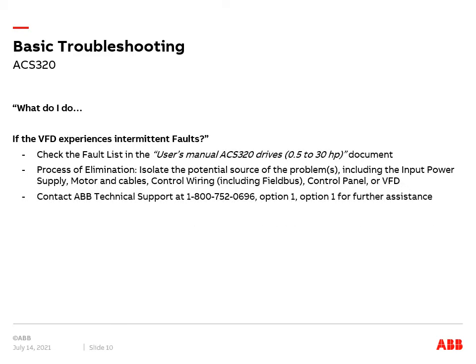What do I do if the VFD experiences intermittent faults? Check the fault list in the user's manual ACS-320 drives 0.5 to 30 horsepower document. Use process of elimination and isolate the potential sources of the problems including the input power supply, motor and cables, control wiring including field bus, control panel, or VFD. Please feel free to contact ABB technical support at the number shown for further assistance.